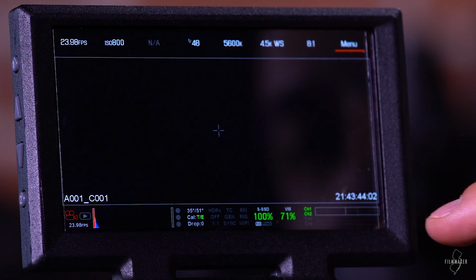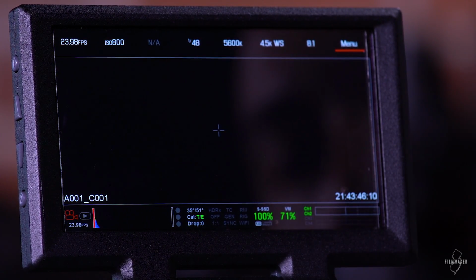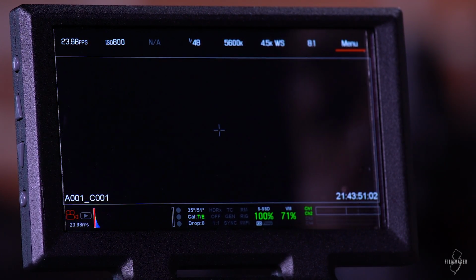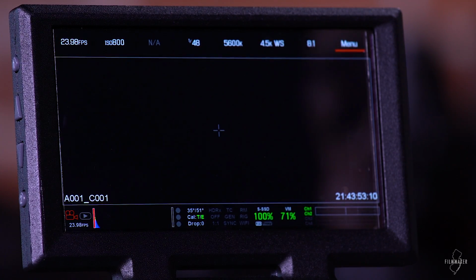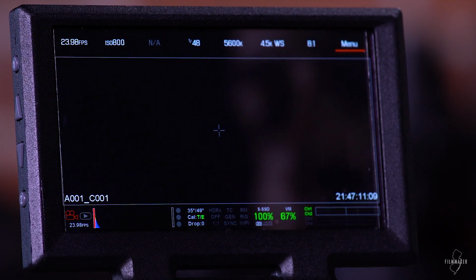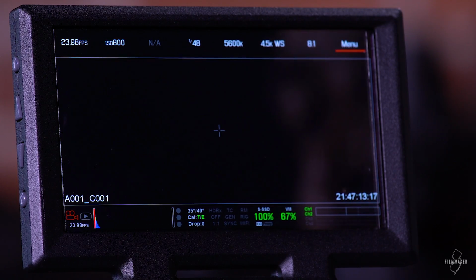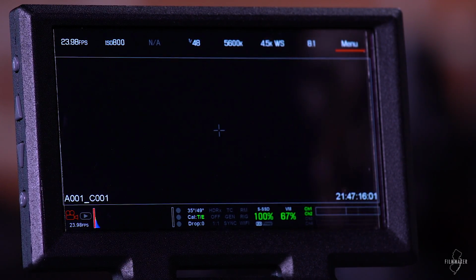One more thing I'd like to show you, which is just on the main menu, and you'll see here, there are 2 temperature readings, and there's a CAL, which obviously means calibration, reading as well with a T and an E. The T and E stand for temperature and exposure. If they're both green, you're good to go. If they're yellow, there's been a slight change in either temperature or exposure. Or if they're red, you should probably stop immediately and make an adjustment by selecting a different calibration map or recalibrating altogether. And these 2 temperature settings that you see above the calibration indicators are the camera's sensor temperature on the left and the camera's core temperature on the right.